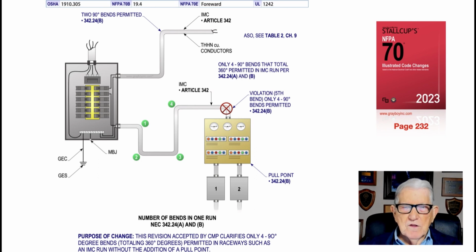Now, this illustration deals with the number of bends in a raceway run, one run. The purpose of the change is to outline that you're only allowed 4 90-degree bends in a raceway system as you route it through the system without installing a pull point for the conductors, such as a junction box or a pull box.